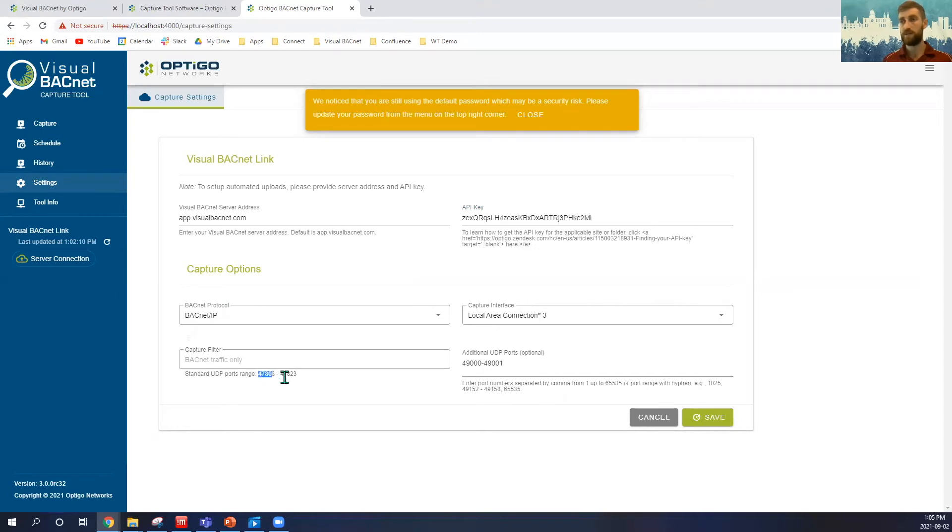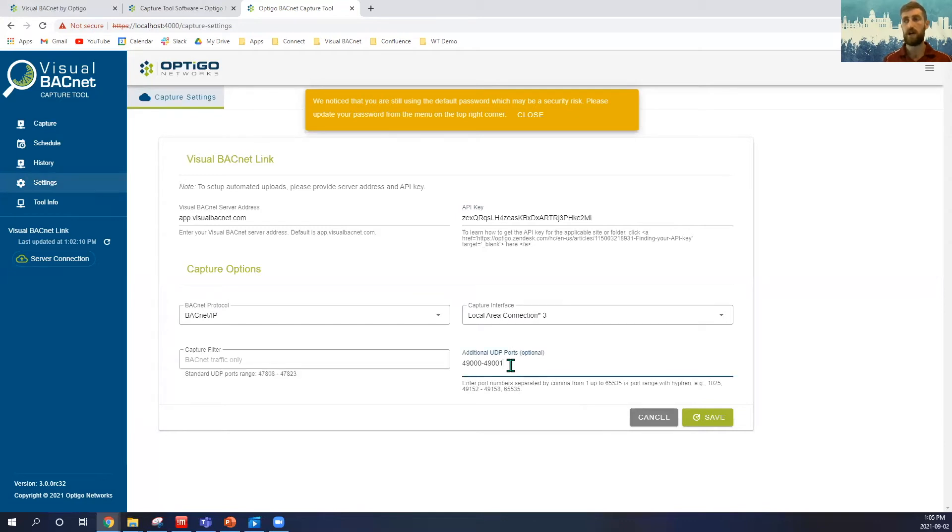By default, we will be on the Capture ports 47808 to 47823, and if you want to add any more ports, we can do so here, separating by a comma for single ports, and with a hyphen or a dash there, if we want a range.